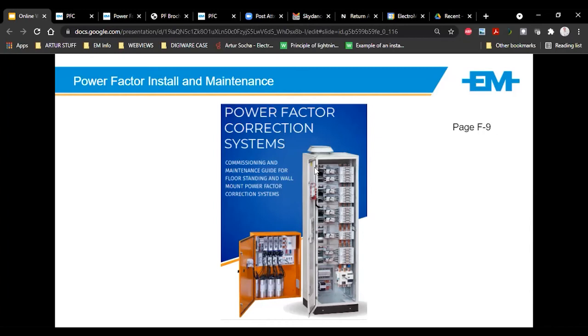Has the load changed? Because quite often what happens is a consultant designs this for an empty warehouse. It says, I need 300 kVA. The system is installed. The occupant of the warehouse comes, puts down a whole lot of VSDs, maybe a furnace, all sorts of things. Now the system is undersized or not protected properly. So you identify within your maintenance whether the load has changed considerably, and whether he's introduced other factors that negatively affect the power factor system.